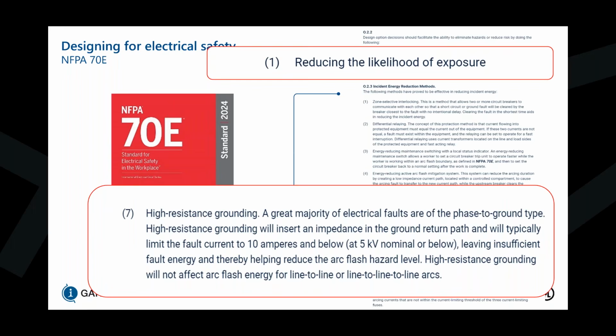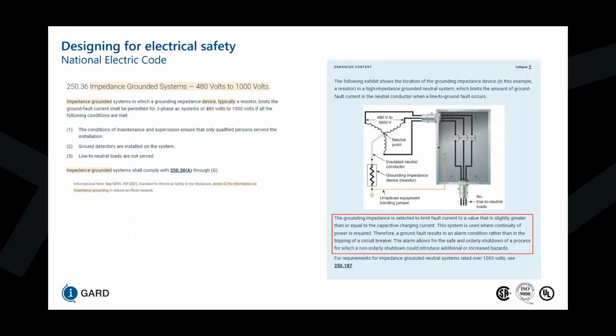The only issue with high resistance grounding is that it will not affect arc flash energy for line to line or line to line to line arcs. In this case, that means a phase to phase or a 3-phase failure. And that's because the current would just circulate between the 2 phases and not go back to the source to be limited by the neutral grounding resistor. So high resistance grounding is really good for phase to ground failures, but it can't do anything on phase to phase or 3-phase failures. Luckily, the majority or 95% of the cases of insulation failure or electrical failure is in relation to a phase to ground failure.